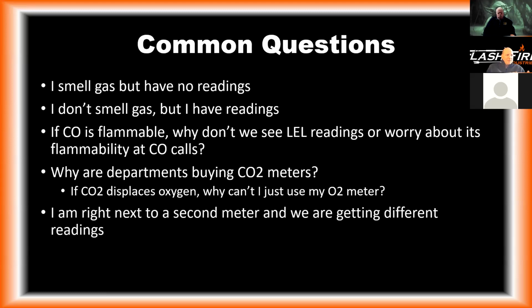I'm right next to a second meter and we're getting different readings. This could be a variety of things. My first question is, are my readings drastically different enough to change my operations? If firefighter A is getting 5 parts per million, firefighter B is getting 10 parts per million, that doesn't really concern me. If firefighter A is getting 50 parts per million, and firefighter B is getting 200 parts per million, then yes, I think there's probably an issue. So what would I do? Well, get a third meter in there, take those 2 meters out, fresh air cal, bring them back in and see how we look.